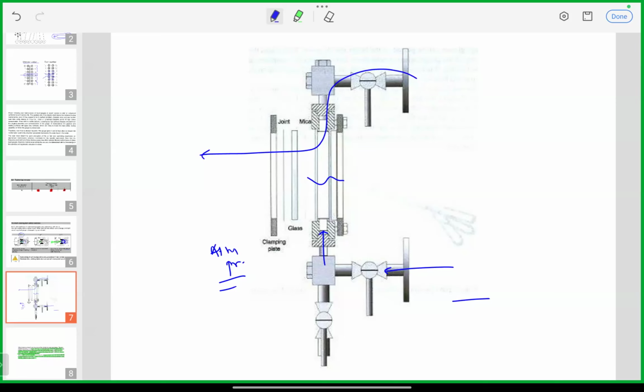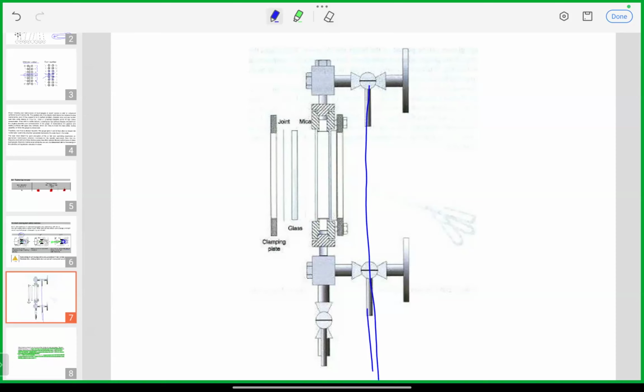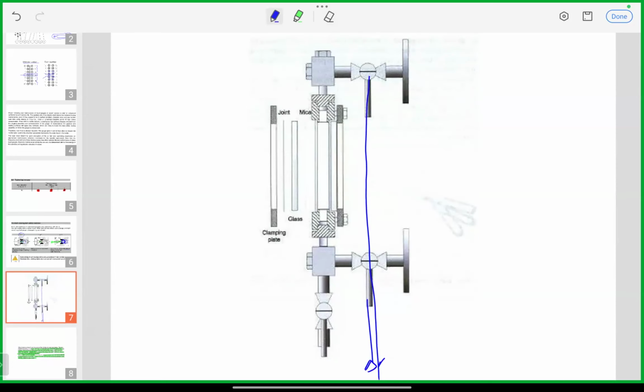But for MMD examination, they will ask only regarding this side. Remember why it is provided on the water side - due to expansion and flash up of the incoming high temperature, high pressure water subjected to atmospheric pressure. Then there will be remote arrangement for operating your valves from the remote location, so the operator is not required to stand next to the gauge glass and operate this valve. Yes sir, sometimes it's near the burner.